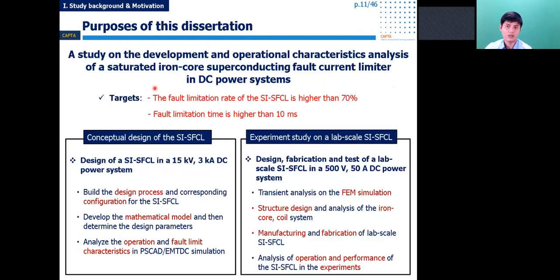In this dissertation, the author developed a conceptual design of the SI-SFCL for the distribution VSC-based MVDC power system, and then a lab-scale prototype SI-SFCL was designed, fabricated, and tested to confirm its effectiveness through experiment. The SI-SFCL was designed with a targeted fault limitation rate of higher than 70% and a fault limitation time of more than 10 milliseconds.